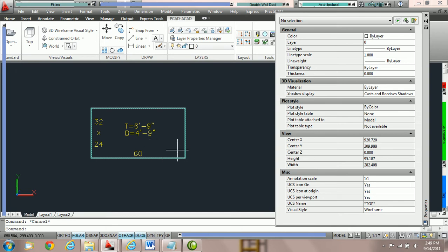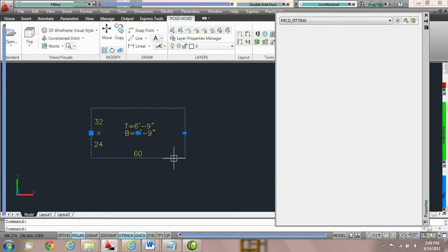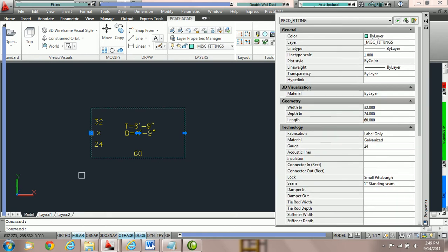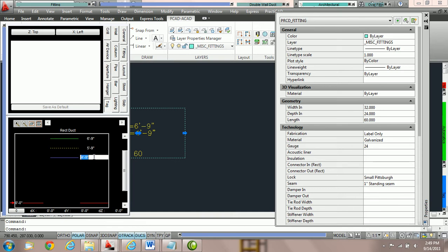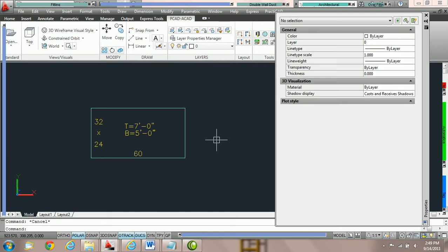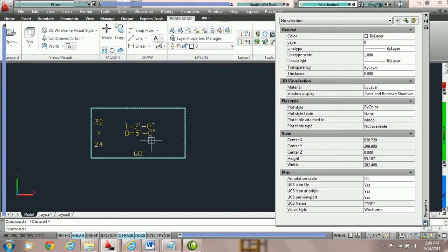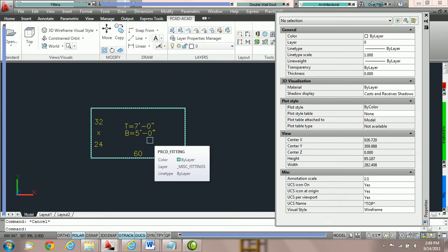This changed the elevation — what was bottom four foot nine is now five foot. To change elevation, all you need to do is click on the duct, go to your elevation box, and you will see all of your choices listed. Simply type in whatever elevation value you want. Here we're going to do five foot, and you can see the tag has reflected the change and the duct has raised up in elevation.